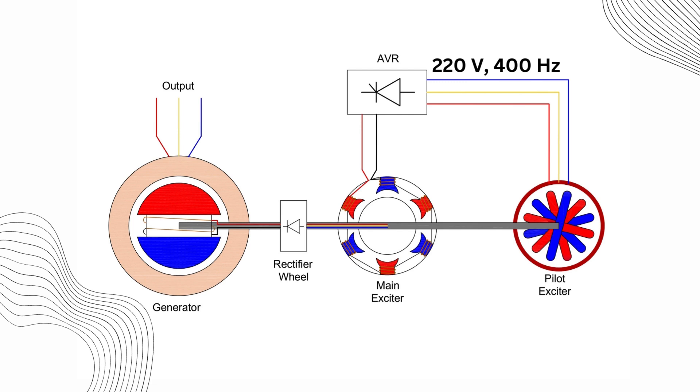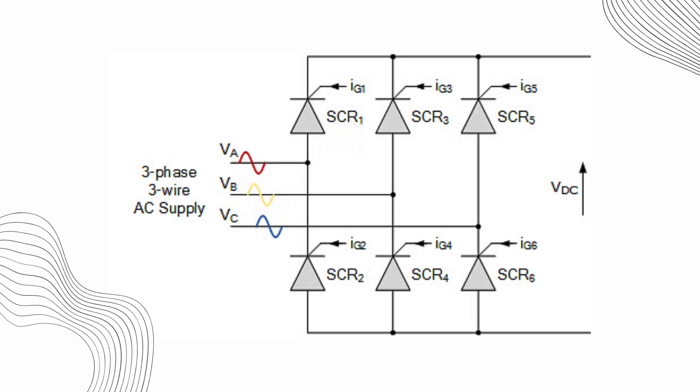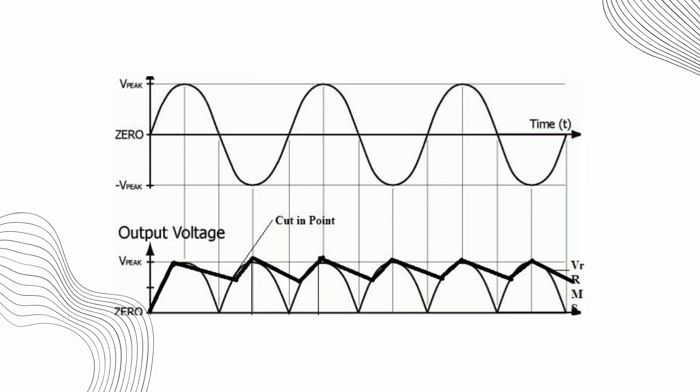But why is this frequency so high? Well, when the AC voltage is fed to the AVR and is rectified to DC by a three-phase fully controlled rectifier in the AVR, a higher input frequency ensures smoother DC output with minimal ripple content, which is crucial for efficient power delivery.